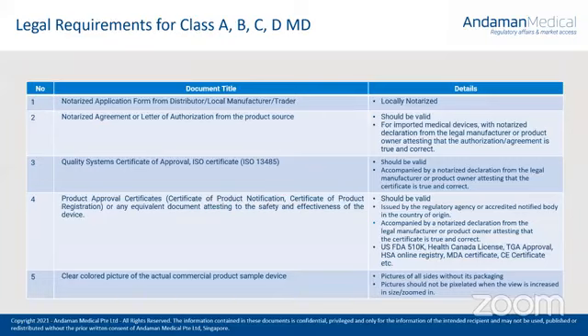Product approval certificates are the next requirement. These are in the form of a certificate of product notification, or a certificate of product registration, or any other equivalent document attesting to the safety and effectiveness of the device. This requirement should also be valid, and it should be issued by the regulatory agency or the health authority of the country, or an accredited notified body in the country of origin. There are many notified bodies who issue ISO 13485. Some of them are TUV and BSI. These are some of the recognized accredited notified bodies.